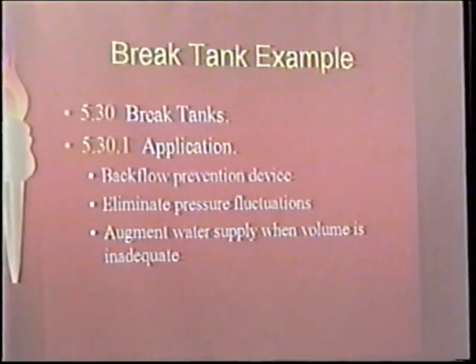In other words, you make your tank big enough, but you're allowed to take into account the gallons per minute that are flowing in from an alternate source, which might be less, as long as the duration is still built into the tank. But the filling requirements are that if you build a 30-minute tank under the break tank rule, the automatic refill still has to operate at 110% of the pump rate. There's a lot of rules in there.